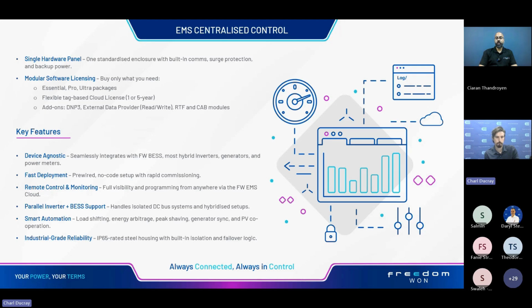The time-of-use schedule set on the EMS is the key way we manage sites to lower max demand usage, enable energy arbitrage, charge batteries using PV, control the PV itself, and control the grid—how much you want to import or export. You can set a limit so you only import a set amount from the grid and no more, and the EMS will handle that by controlling the inverter and batteries accordingly.